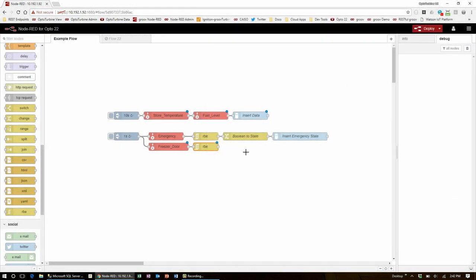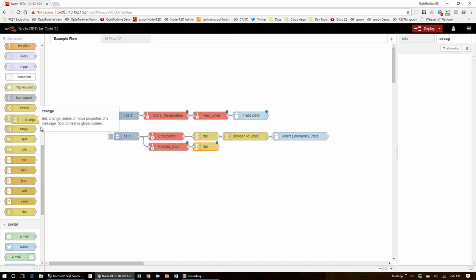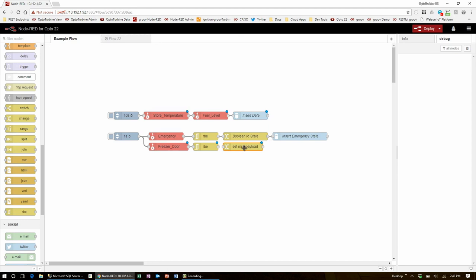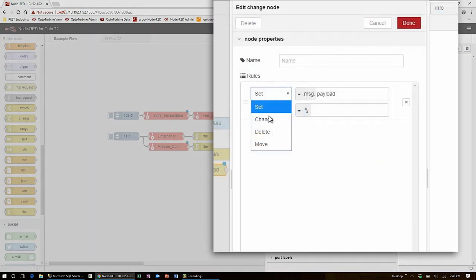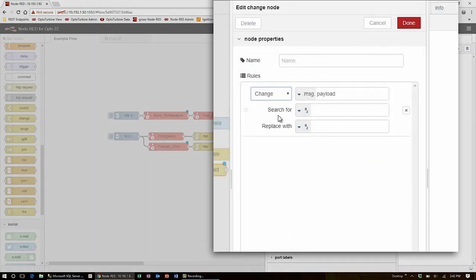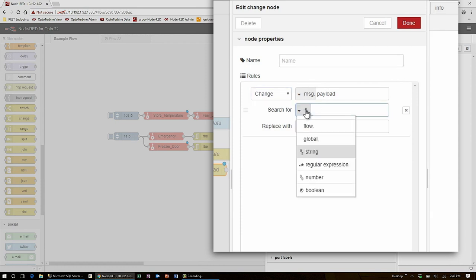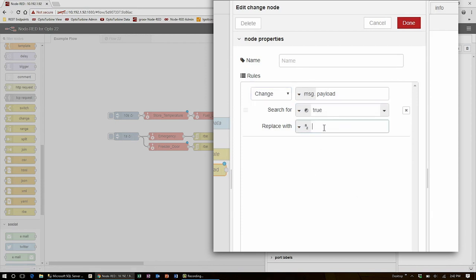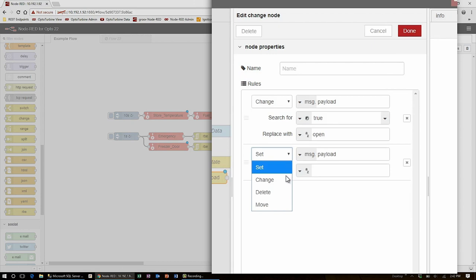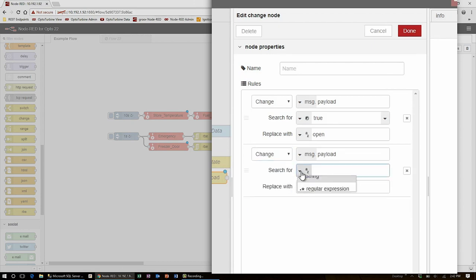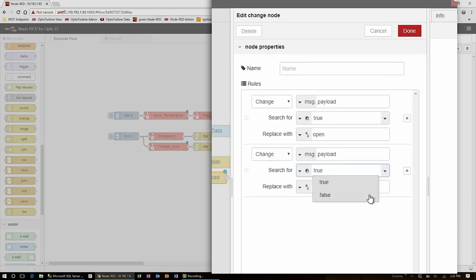Now I have the true false value from the freezer door, but that's not very descriptive. So like emergency, I will bring in a change node. Here, I'm going to add some rules to edit the strings that are in payload. I'm going to change the message.payload and search for the boolean value true, and I'm going to replace that with open. Then I can add another rule, and I'm also going to change message.payload and search for the boolean value false, and then I'll replace that with closed.